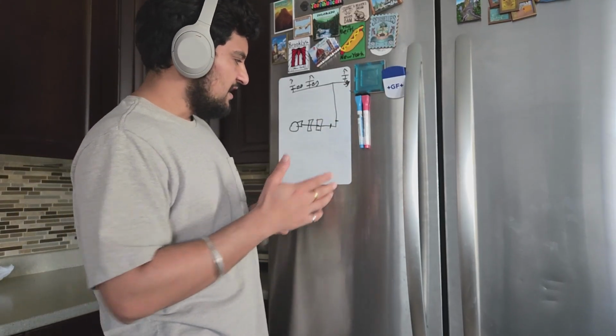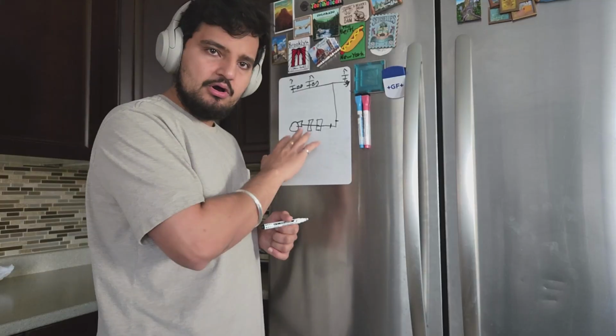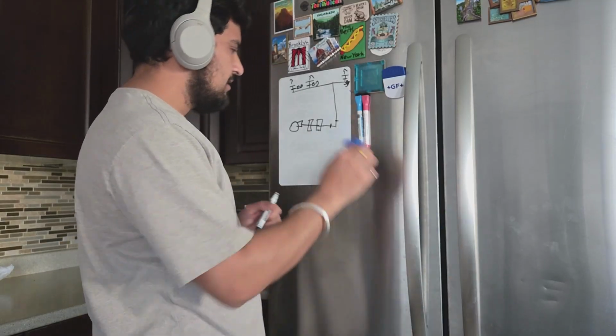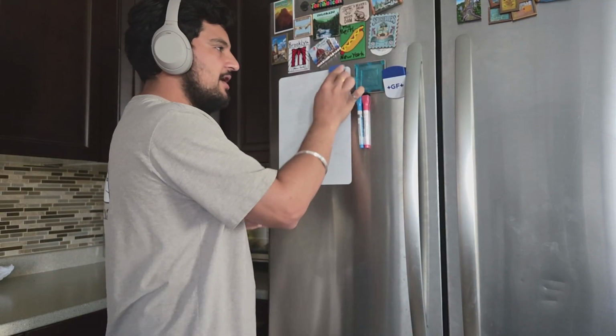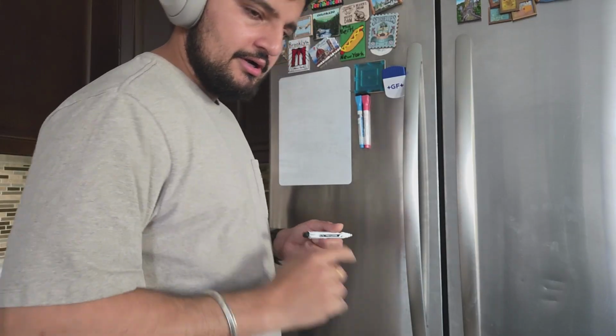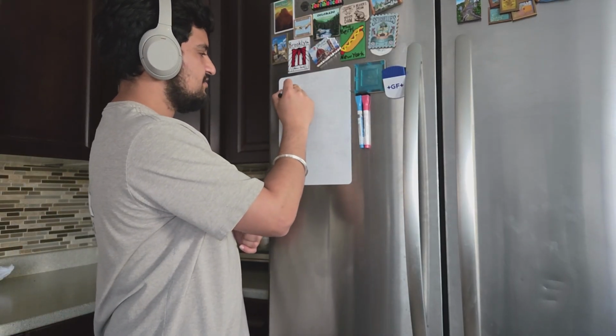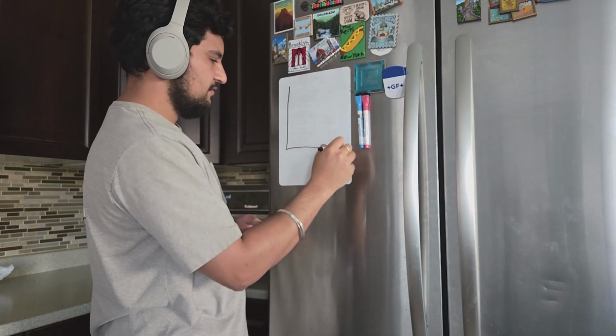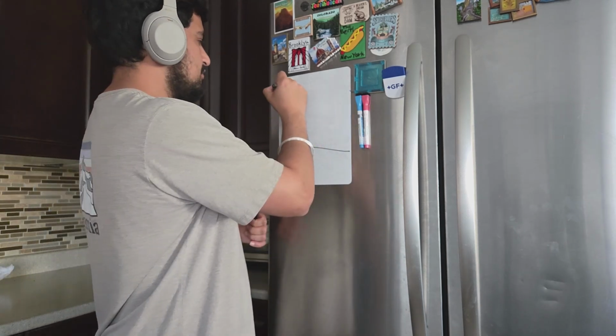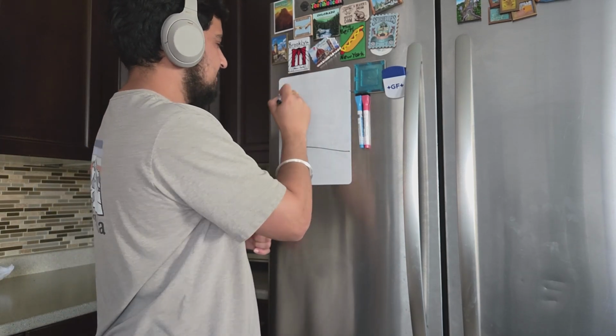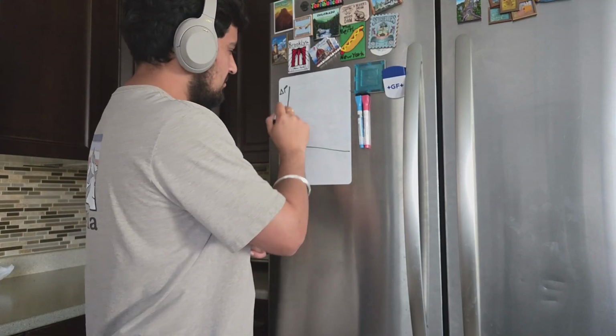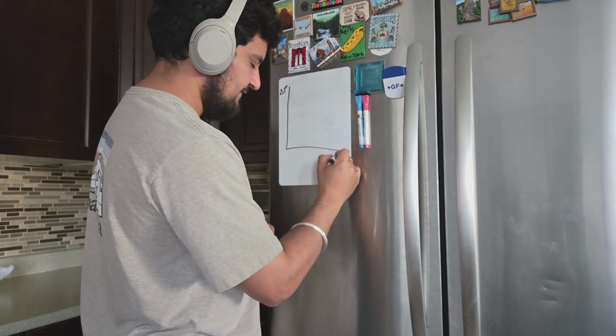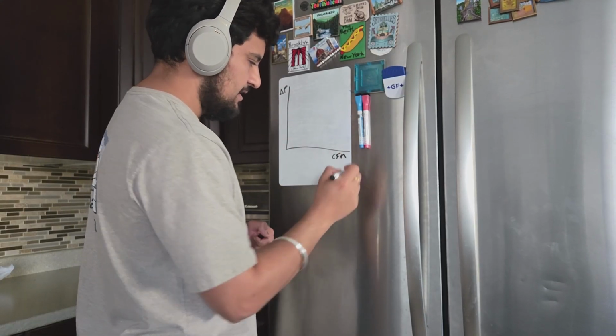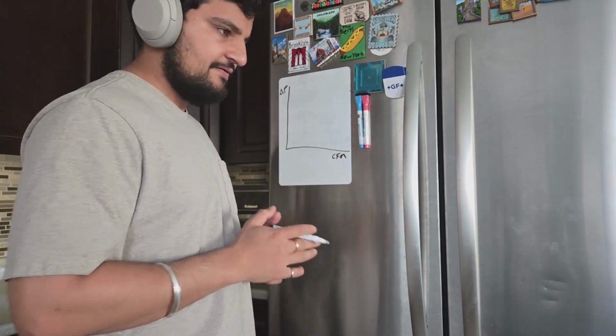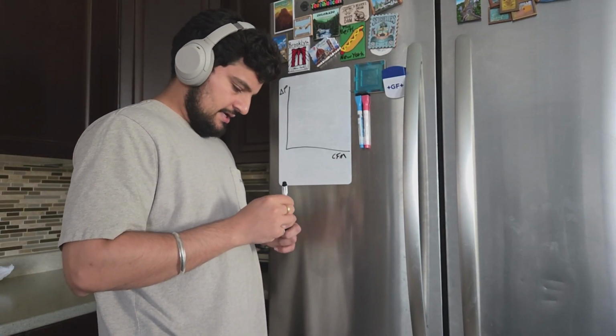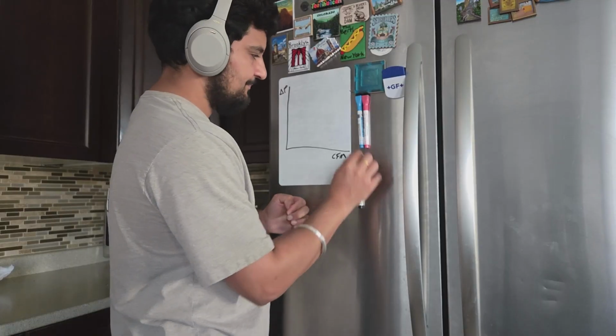Now, let's assume there's something causing a change of pressure into your system. Let's talk about how this affects your ductwork, right? So let's draw a little graph here. That's really going to help us. So here's the graph. You have pressure loss delta P on the y-axis, and then you have flow rate. We're going to call it CFM, cubic foot per minute. That's how we measure flow rate in the industry. And we're going to draw something here.